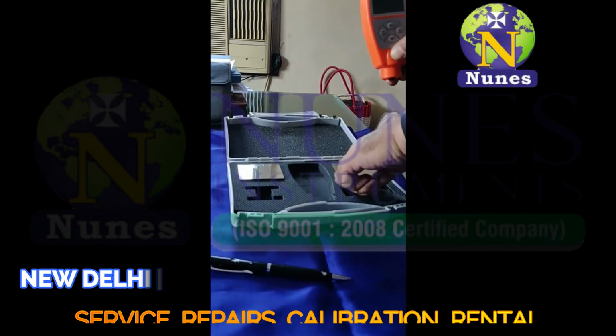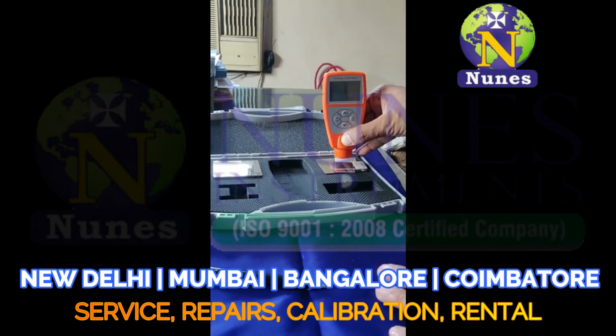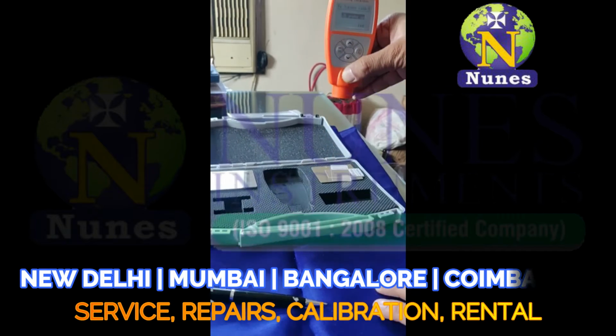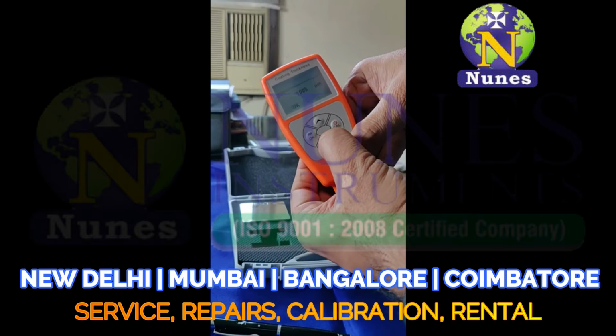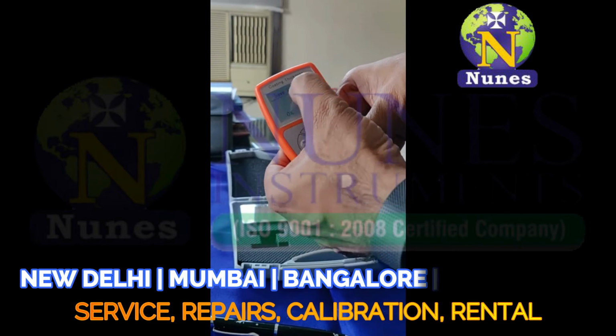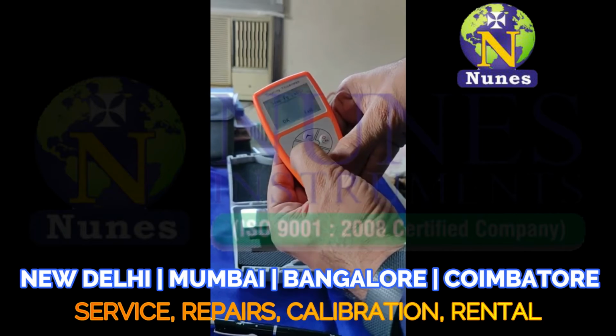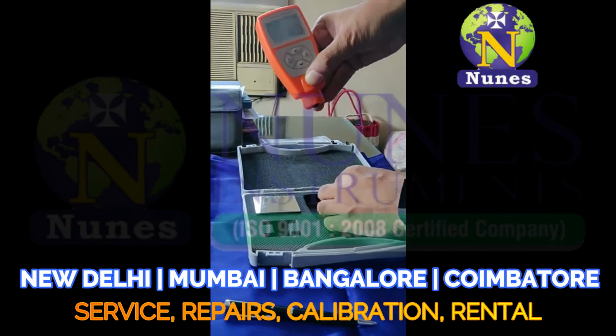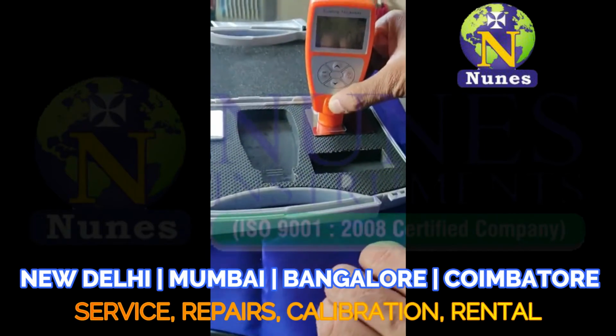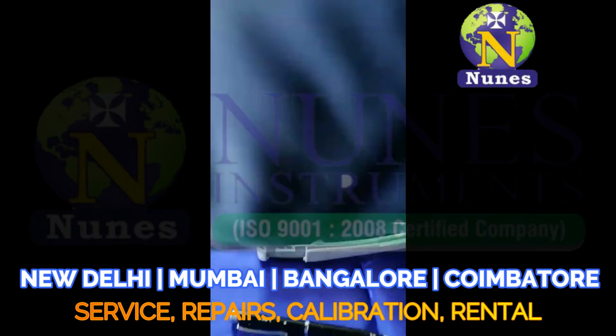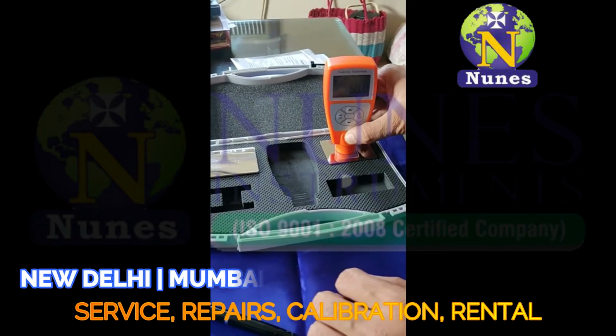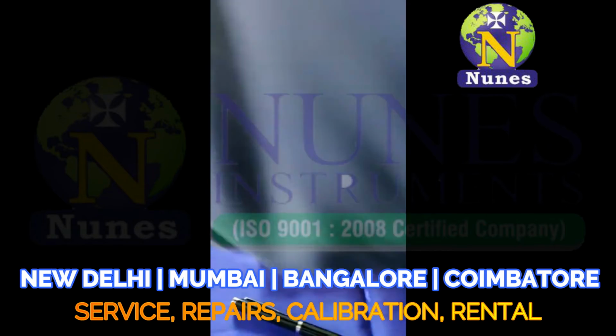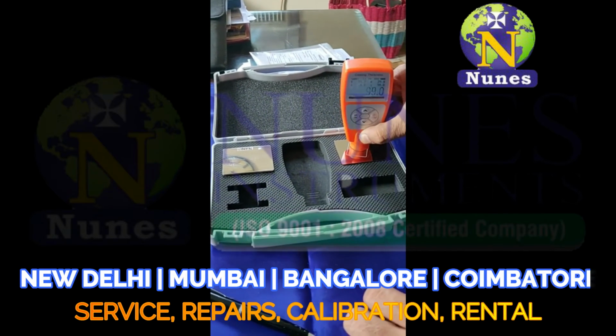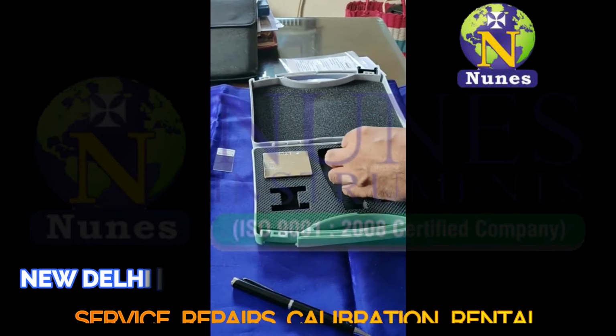So we take 502 and 502, two coatings, and it says 1011. It should be 1004. Okay. So it says save ferrous calibration, and we say okay. So this particular component is calibrated. Now we'll try taking the reading again. On 50, it shows us the reading of 50. On 98, it gives us a reading of 99. On 250, it gives us 253, which is within the range.